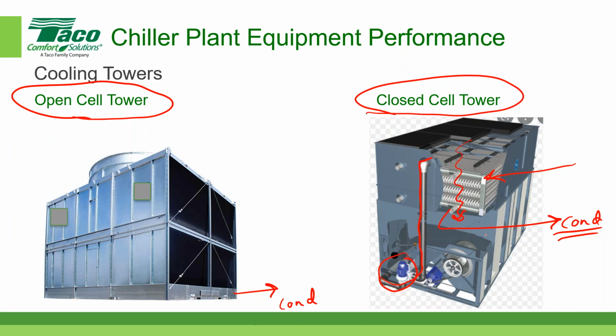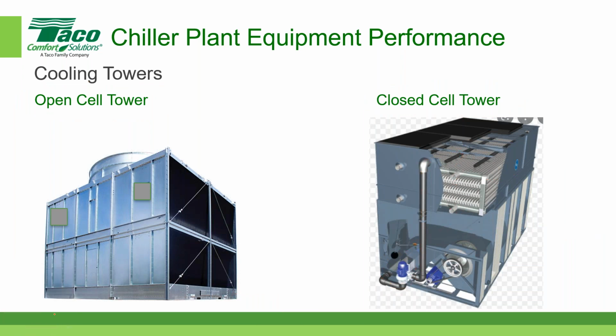But for cooling towers, for the majority of larger chiller plants, if it's a water-cooled system, chances are it's going to be an open cell cooling tower. So those are the differences between those two major categories of equipment.